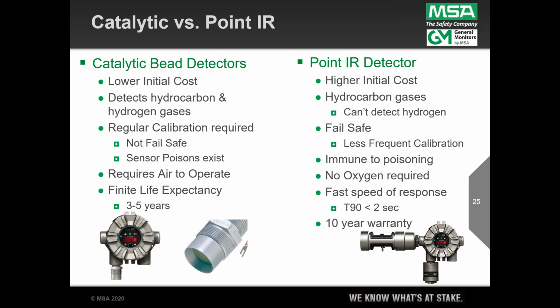Now, point IR detectors have a higher initial cost, right? They're a little more expensive, not much, but they don't detect hydrogen. That's the other thing I didn't talk about initially, but cat beads are really the one gas detector that is required for hydrogen. You have to have a cat bead for hydrogen. But point IR, they're great for your C1 through C7 hydrocarbons, but they can't detect hydrogen. They are fail-safe, though. I mean, fail-safe in the internal failure mode sense. They don't require the same level of calibration. They don't have any poisoning impact. They don't care about oxygen. They don't need oxygen for their measurement. They can be very fast speed of response, and of course, ours has a 10-year warranty.